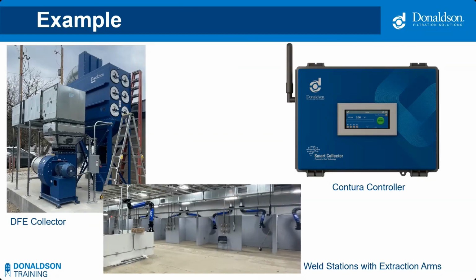Thanks, Carla. Here you can see an example of a pulse jet cleaning collector, in this case a DFE, that was recently installed at a weld shop, or a weld school potentially. You can see in the bottom image all the different weld cells with the associated extraction arms. But the collector is located outside, so the controller was not mounted to the collector itself. It was mounted inside the facility remotely. This basic custom control panel, very similar to one Carly just described, has a digital readout with the ability to set the high and low cleaning set points, trigger alarms if there's any issues, and start-stop the collector from inside the facility.